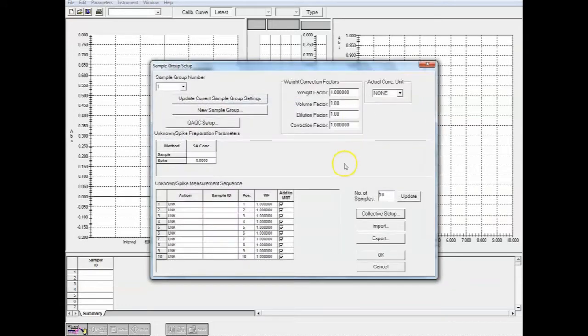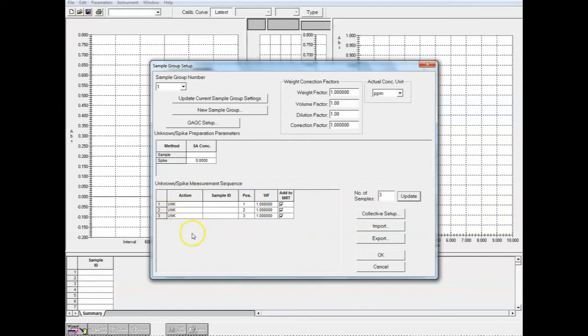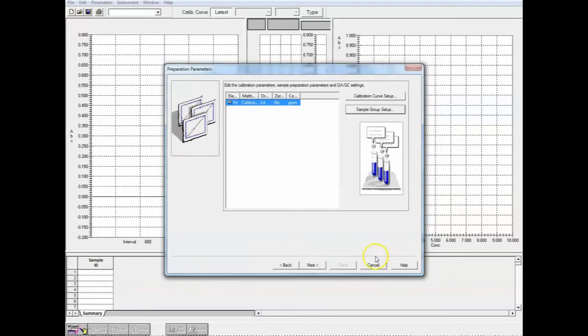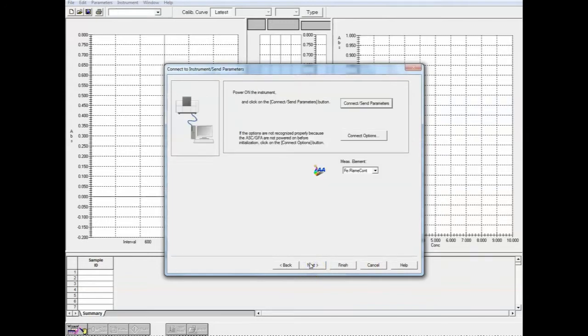There's also a section for sample setup, so we can tell it how many samples we want to run. And again, we can put in weight correction factors up here, but we're not going to bother with that. We will tell it what the units are, so the units for our samples we want to be the same as our standards, so we'll change that to ppm. And in this lab we ran 3 samples. Okay, so we're going to update that, and you'll notice that our sample table then changes to just 3 lines. And we have the ability here to put in names for our samples or sample IDs if we want to. Since we only have 3, we labeled them A, B, C. We're just going to leave them as they are. Okay. We'll select OK. And next. So we're just going through step by step.